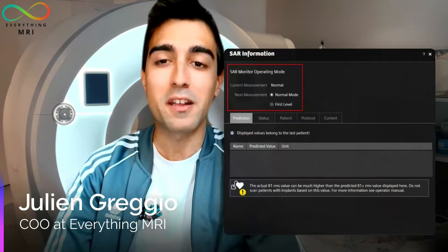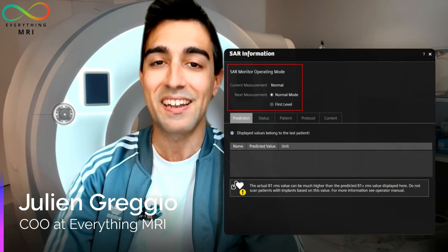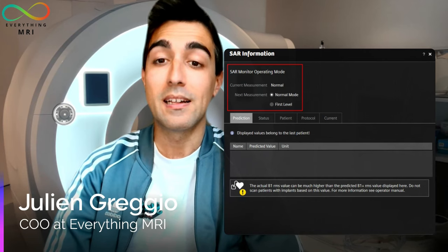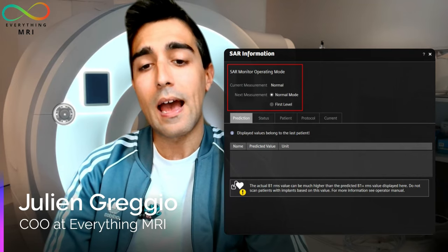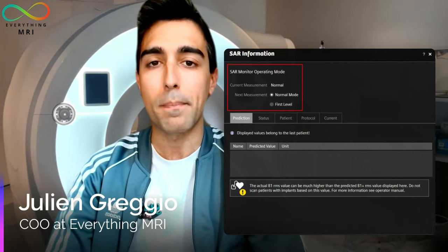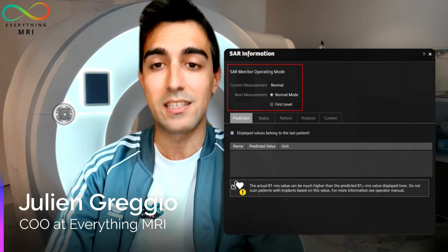The first thing we need to know is that there are three main modes of operation for an MR scanner as far as monitoring the SAR is concerned. These are normal mode, first level, and second level. As you can see from this table, in most clinical settings we just deal with the first two, namely normal mode and first level. The use of second level is fairly limited at present, as it is predominantly used in some specific research settings.